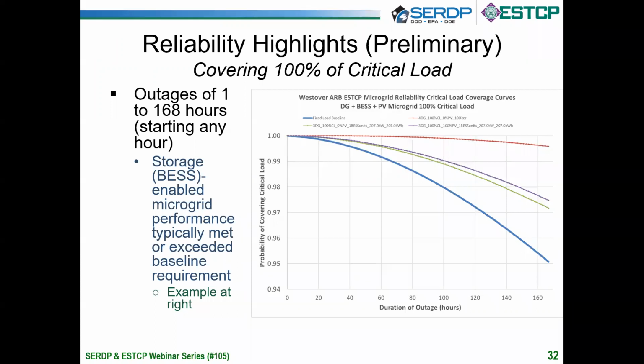The second interesting observation is that when one of the 4 generators in the Westover microgrid can be removed when you add storage, that's represented by the green and purple lines, they still beat the baseline requirements. So that's important because it speaks to whether overinvestment in diesel generators can be reduced if you add storage. If you can do that while meeting or bettering the reliability requirements, you save $560,000 of capital costs for each of the 750 kilowatt new generators, plus $7,000 every single year in O&M and testing costs for the generator.